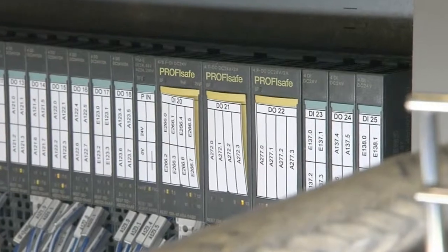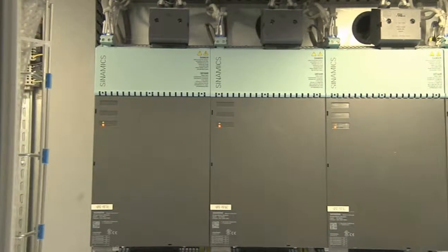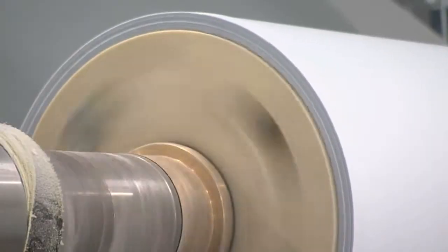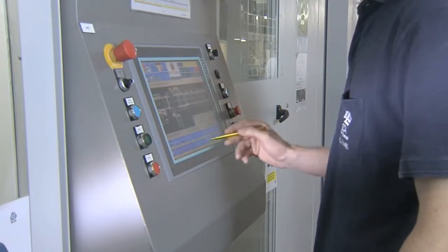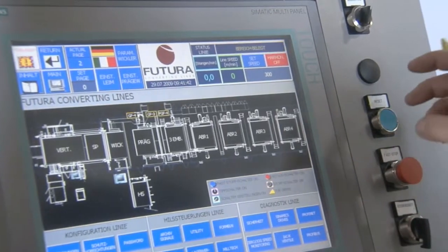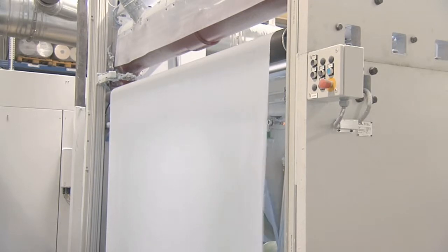For the logic part, we have an S7 CPU. The individual aggregates have their own control unit, connected to the SINAMICS axes, and handle all computation for the servo parts and the virtual axis in the machine. This virtual master is responsible for displaying the line speed and transferring it to a real servo axis. The operator can enter slip values and leading and lagging values of every single roll directly on the multi-panel without stopping the machine, and in this way react to quality defects.